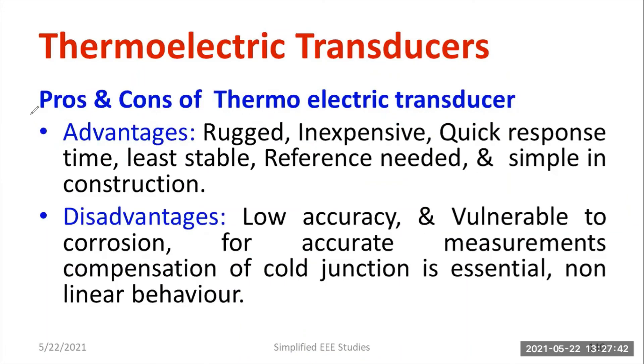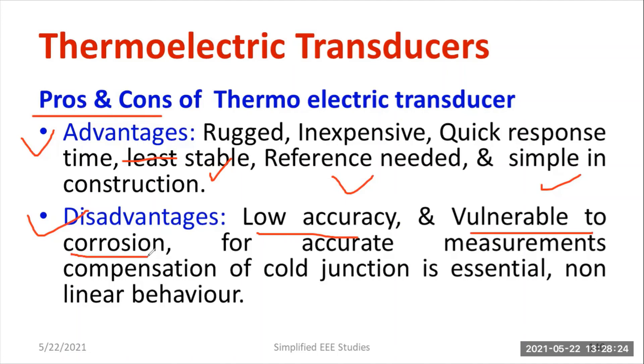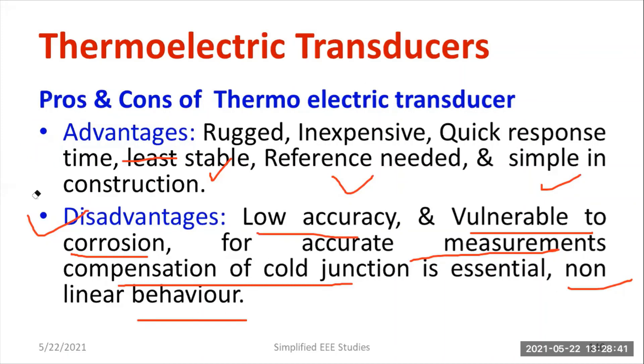Regarding advantages and disadvantages: advantages include rugged construction, it is cheap, the response time is very fast, it shows high stability for a certain range, and it is simple in construction. Drawbacks include low accuracy, as the cold junction requires calibration and compensation. It is vulnerable to corrosion, requiring stainless steel which is expensive. Temperature compensation for the cold junction is also expensive but essential — otherwise you may get wrong readings. There is also non-linear behavior for certain ranges.